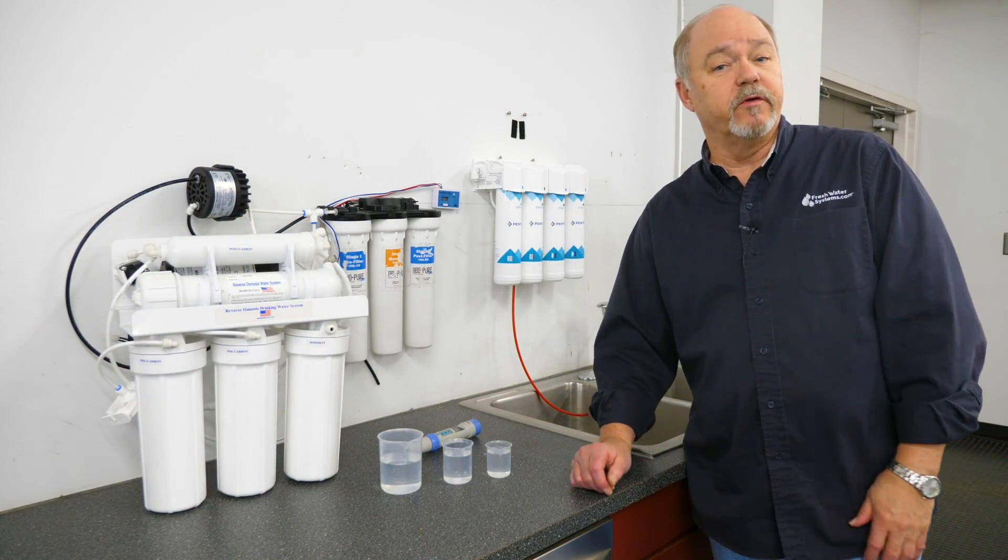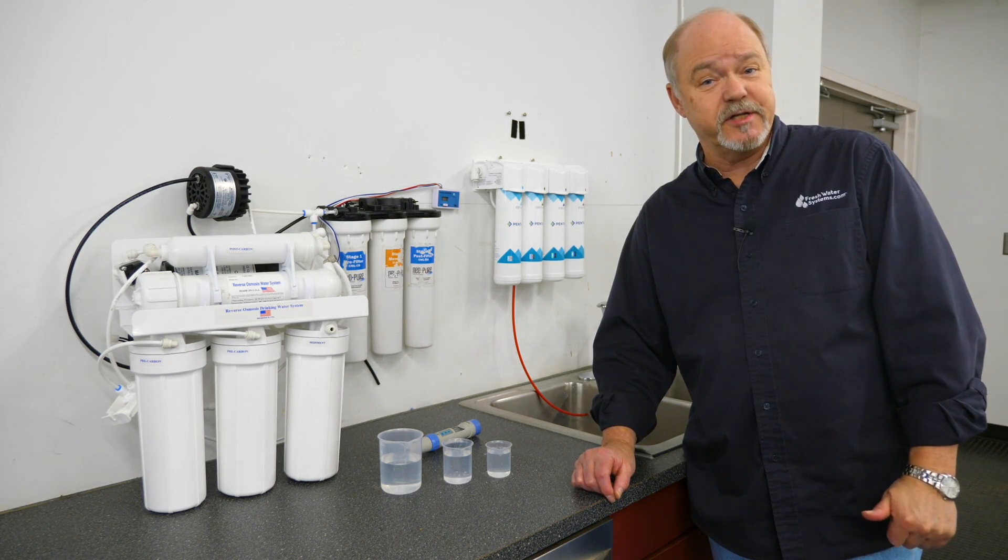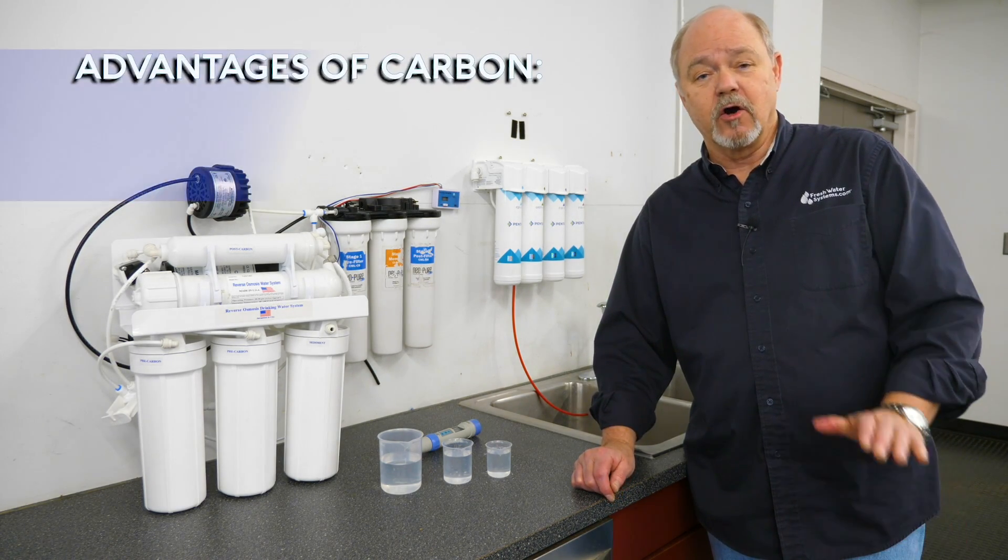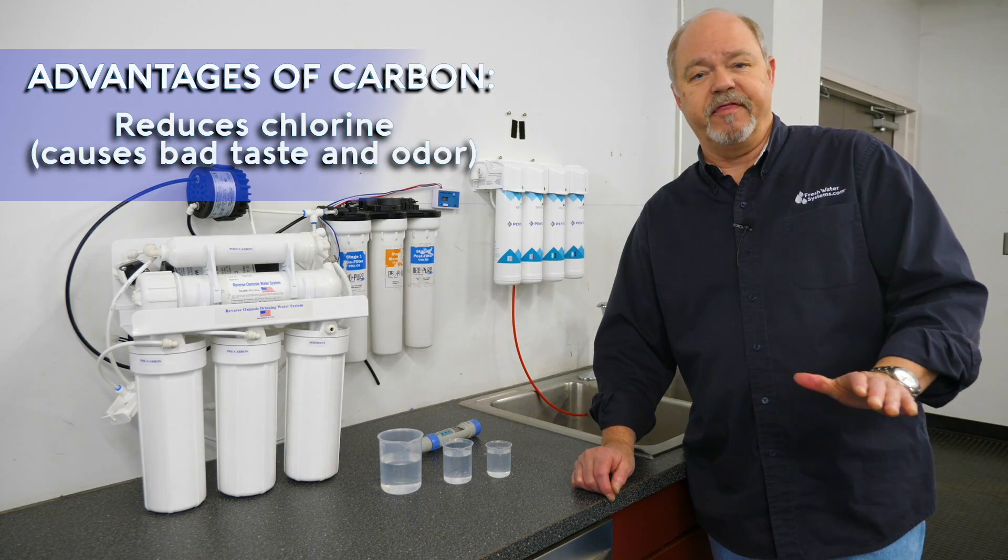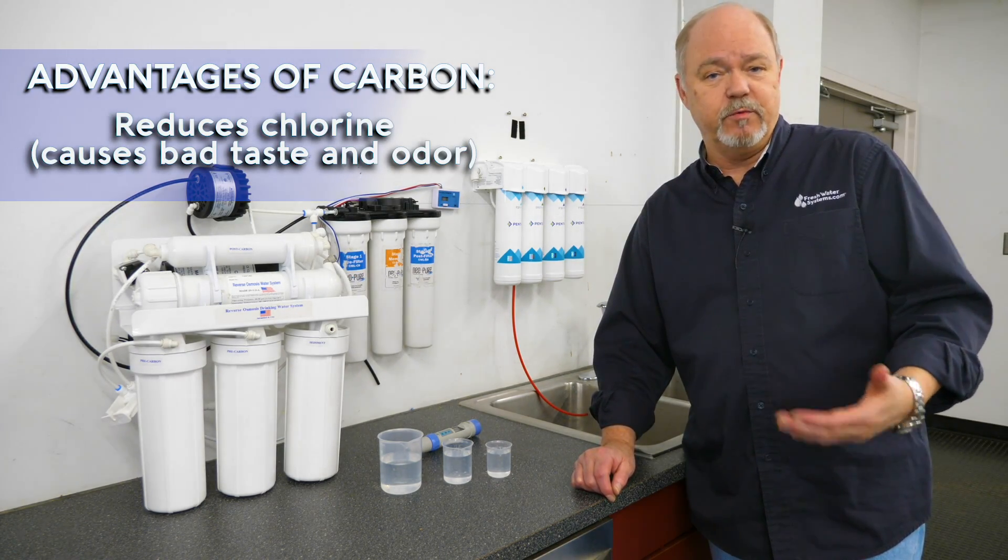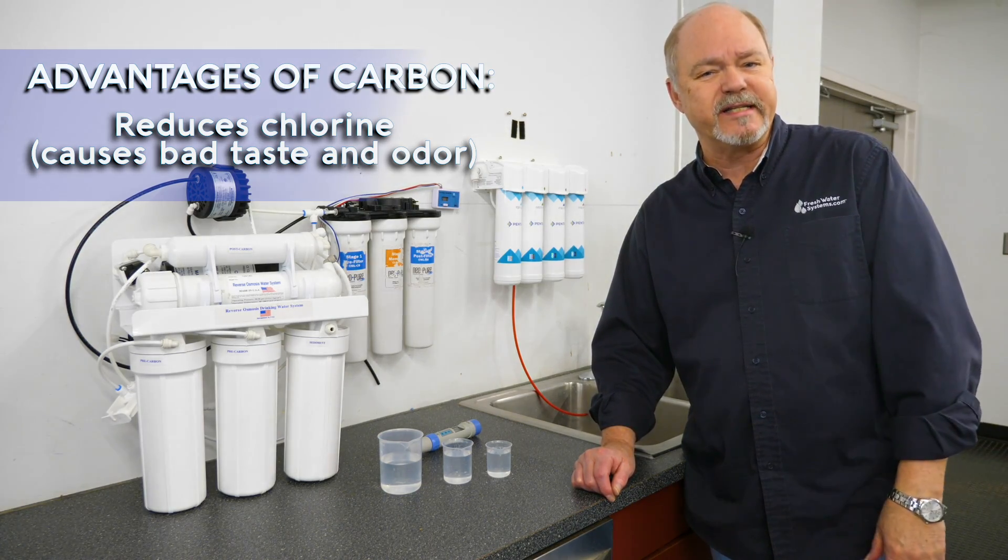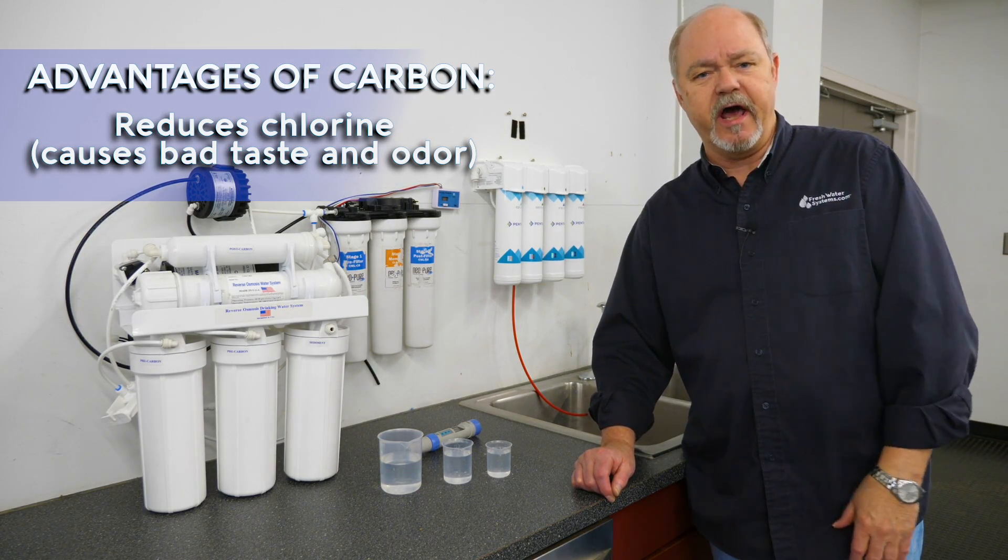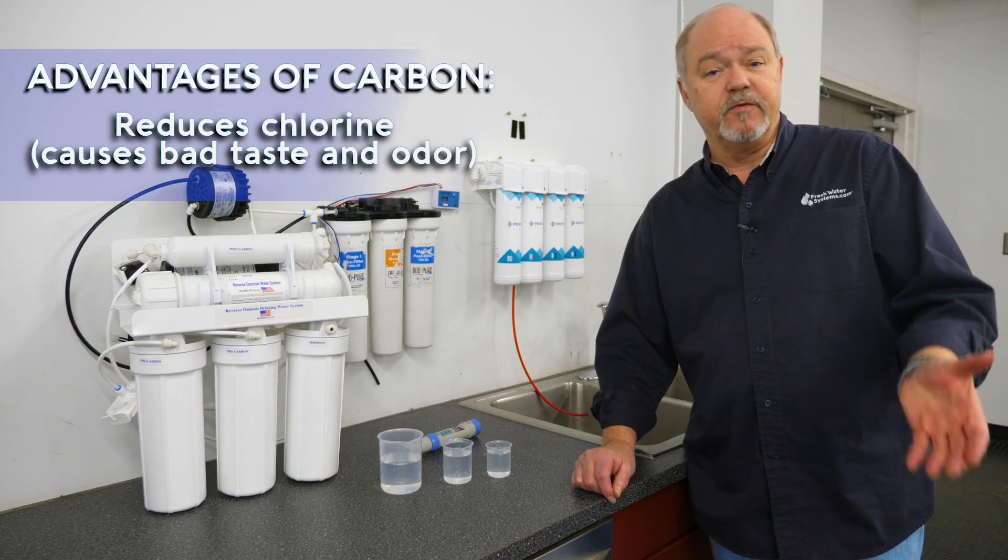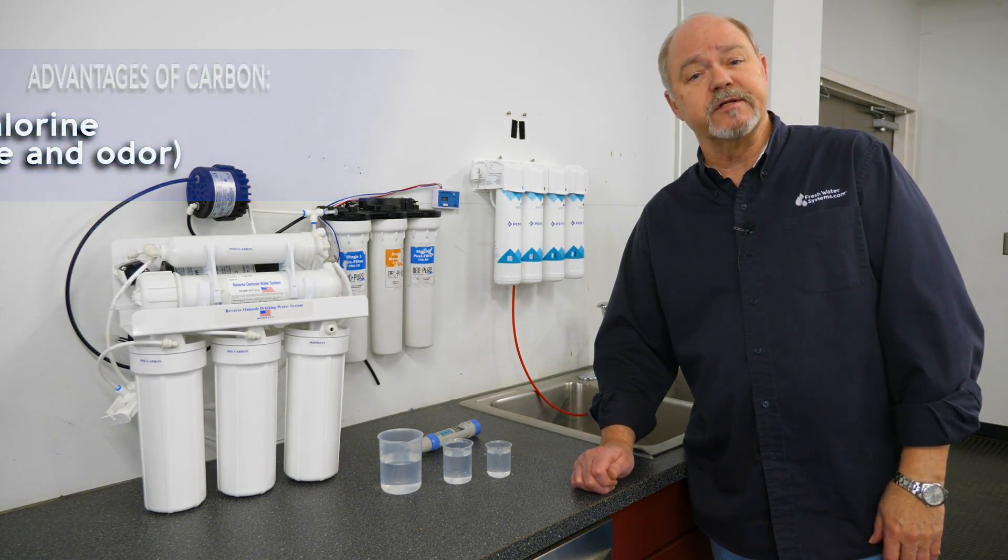The best way to understand whether or not your carbon filter is working a lot of times is with your taste buds and your nose. Carbon is going to be taking out things that cause taste and odor. In fact most of the time when you buy a carbon filter that's what you're buying it for is to get rid of the chlorine taste and odor that you have on city water. And if you start to smell or taste that again pretty good bet that the carbon filter is exhausted.